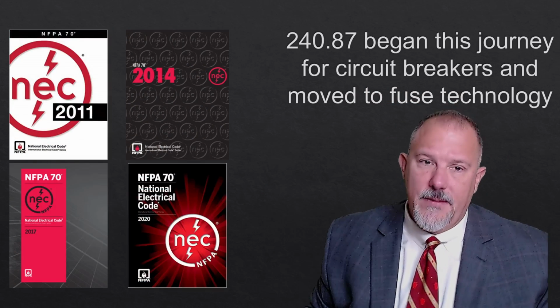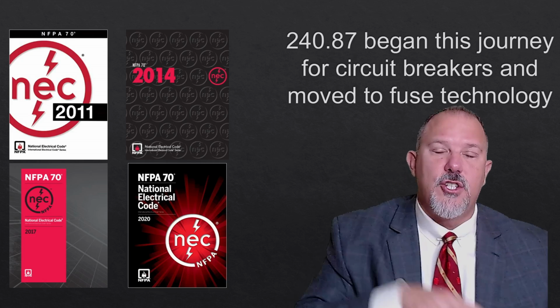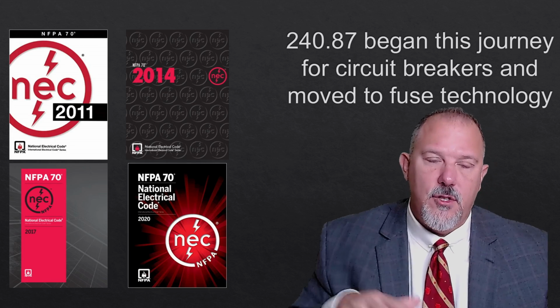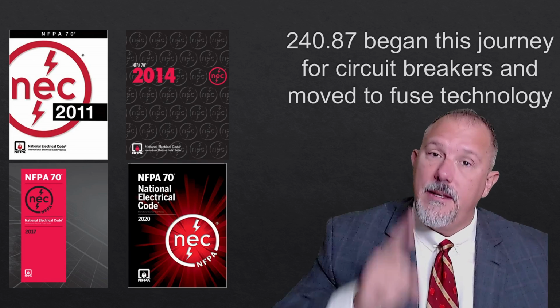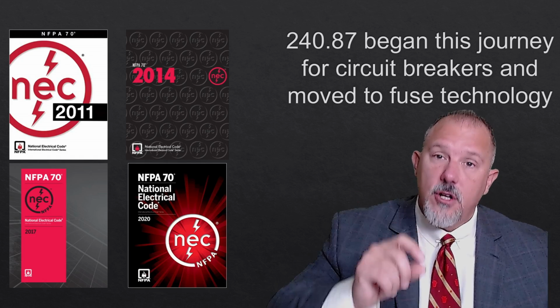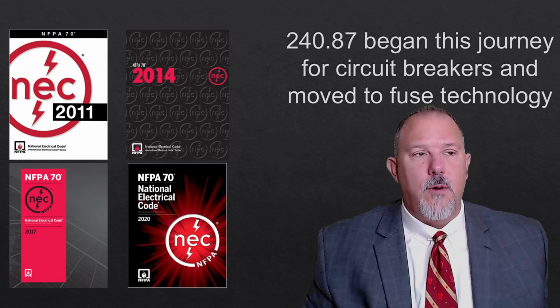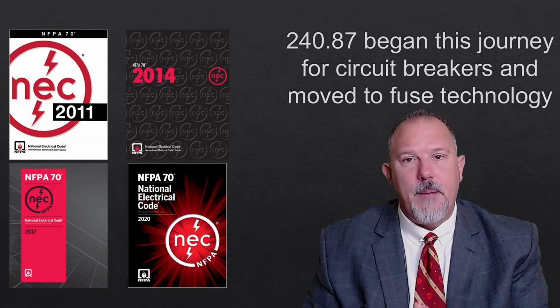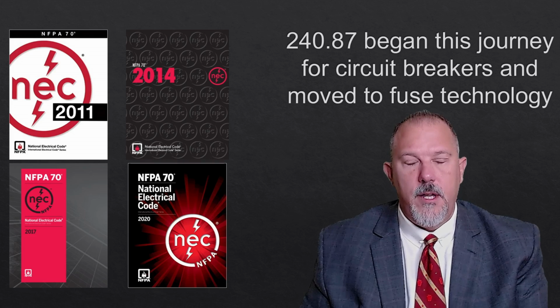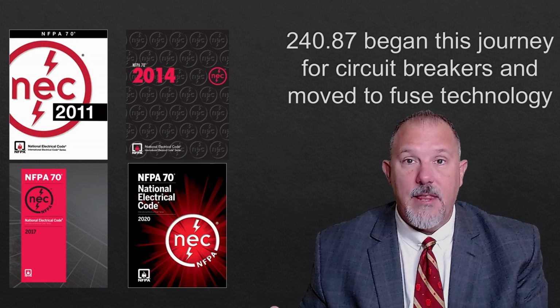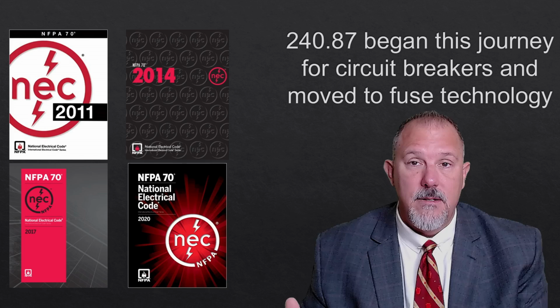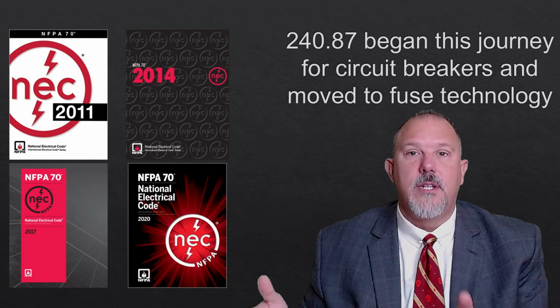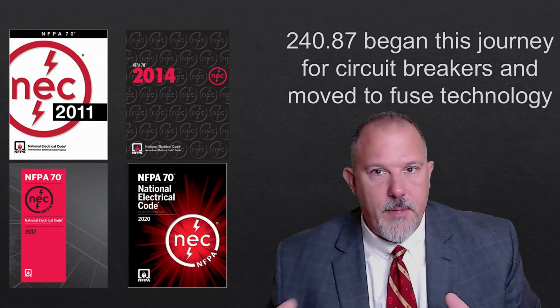Now, 240.87 began its journey in 2011. The 2011 National Electrical Code only impacted circuit breakers without an instantaneous. And what was that targeting? That was targeting the big power circuit breakers that had a 30 cycle delay and had no instantaneous. And I call those the double wides. Those are big ones. Those are big breakers.